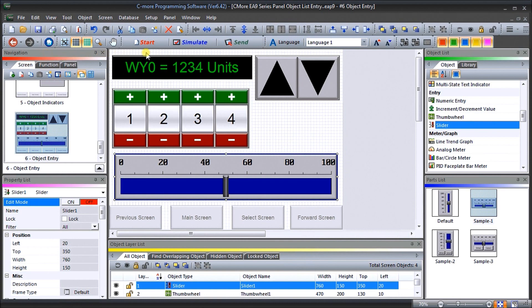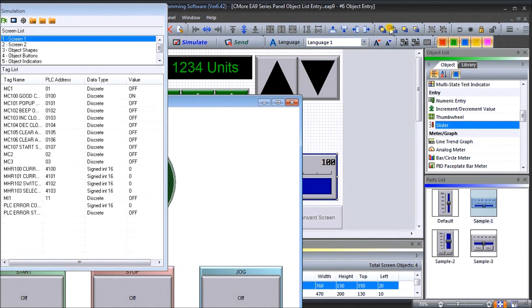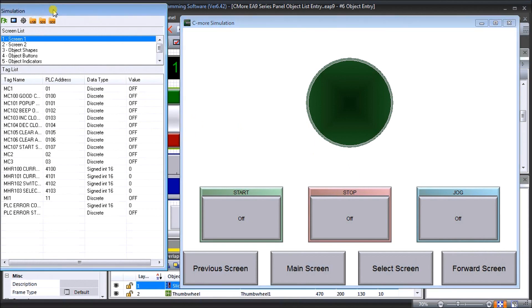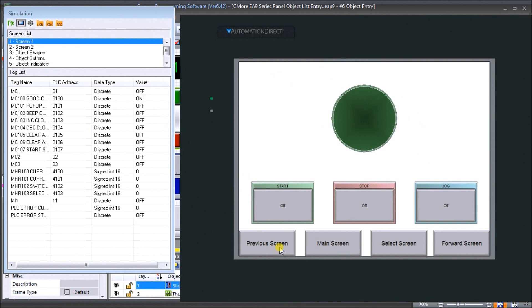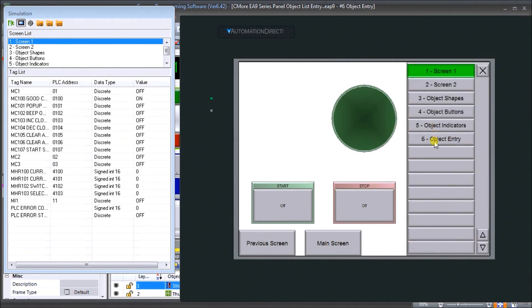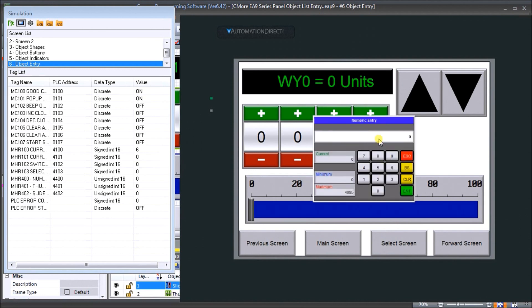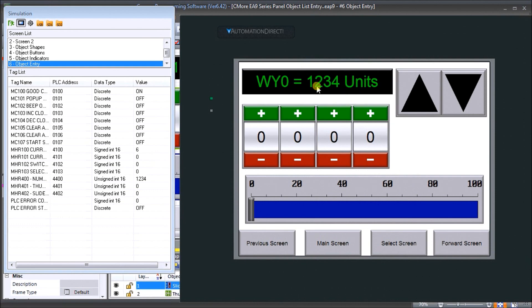Now we can simulate this. We'll hit simulate with the EA9 T10 CL and start. Here's our simulator with the simulation control. We can change the bezel so it looks like an actual T10 CL. Selecting our object entry screen, I hit my WY0 numeric entry and a keypad comes up. I'll enter 1 2 3 4, hit enter, and 1234 appears, also showing under MHR 400. Incrementing goes up by five, and decrementing goes down by five — everything looks good.